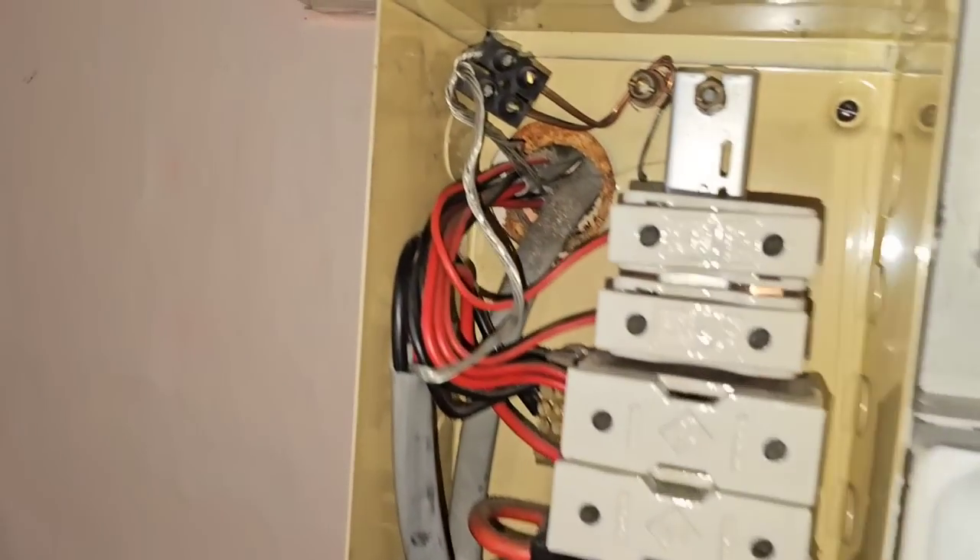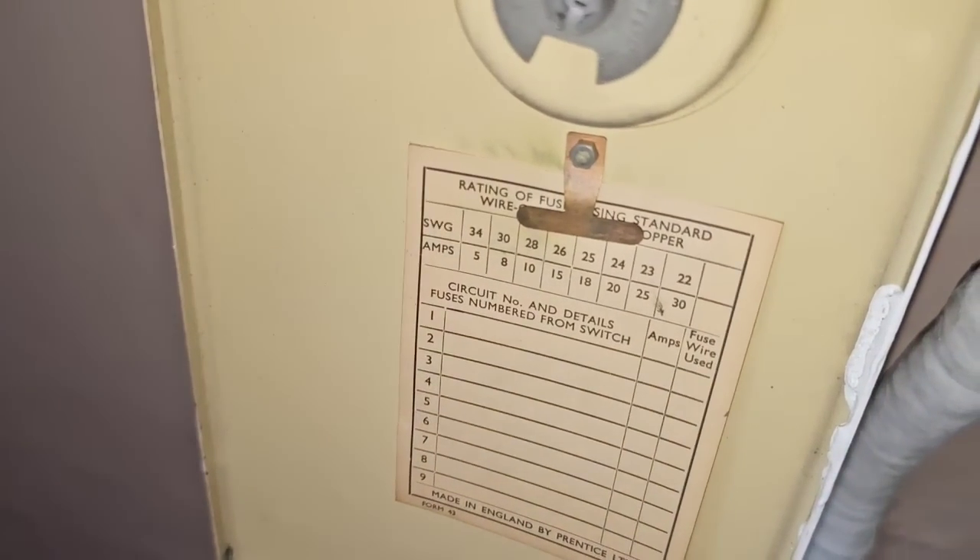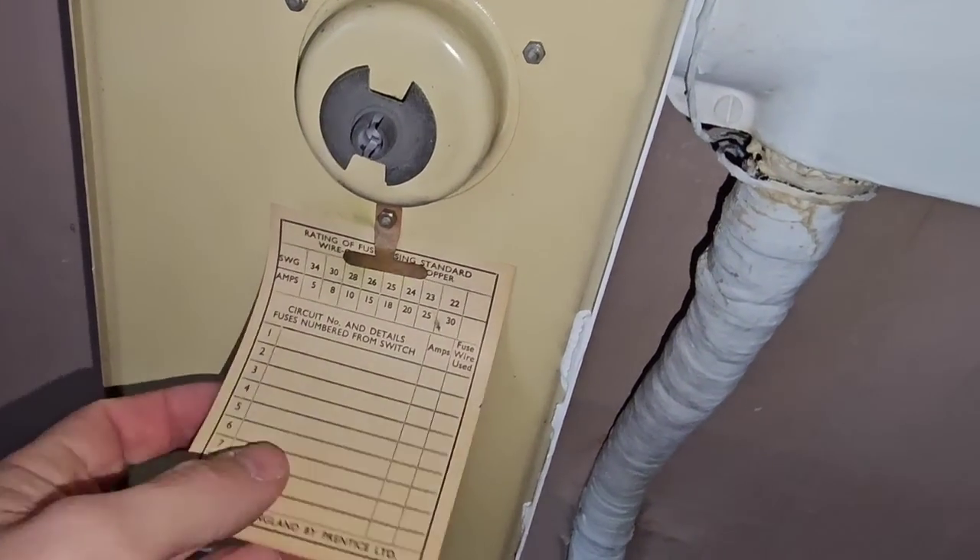The fact it's got CPCs on the lights means this installation — it's not been tested yet — might still be able to be used. I'm not saying it shouldn't be upgraded because it's very old. However, if the insulation resistance comes back okay, the ring final circuit's in good condition, and there is an earth at every point, it's still okay for continued use. I might recommend it's upgraded — the house has just been bought, it might make sense to get everything rewired now while it's empty, which is more cost effective than future damage.